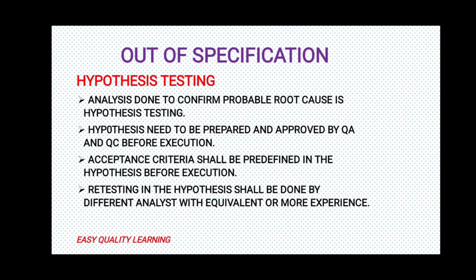So, before proceeding to your analytical investigation, we need to understand hypothesis testing because this particular term will be used during your analytical investigation. So, what is hypothesis testing? Analysis done to confirm the probable root cause is hypothesis testing. So, whatever analysis we are carrying out for confirming the probable root cause, that is hypothesis testing. The hypothesis needs to be prepared and approved by QA and QC before execution. So, QA and QC shall be in agreement on what we are going to do in the hypothesis. Acceptance criteria shall be predefined in the hypothesis before execution.